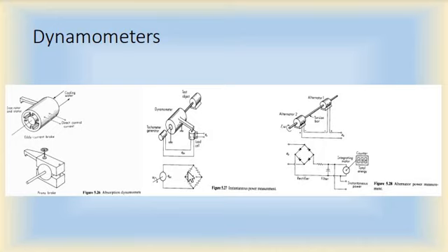So this is the bridge circuit. Here you can see four resistances connected corner to corner. This is the bridge circuit, and this is the rotating shaft. This is the figure of the measurement. Here the speed is measured by this DC tachometer generator, and the output of the tachometer generator is a DC voltage, and this voltage is applied as the excitation voltage of a strain gauge load cell. This is the strain gauge load cell, and the load cell is used to measure the torque.